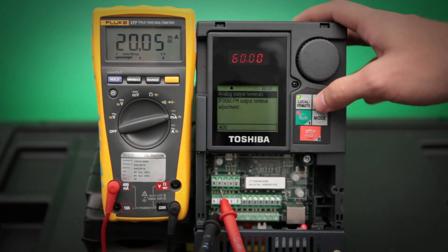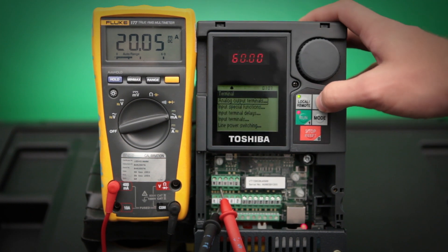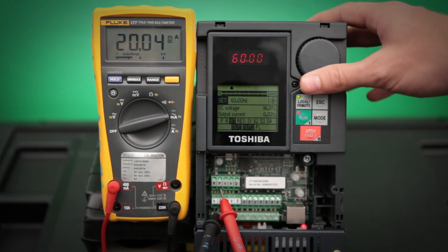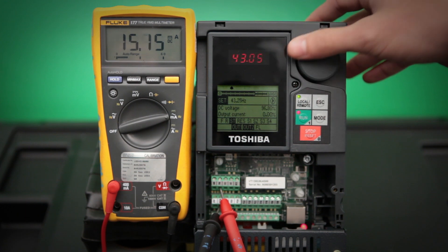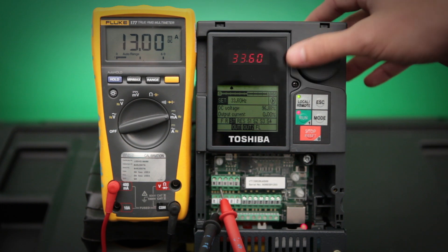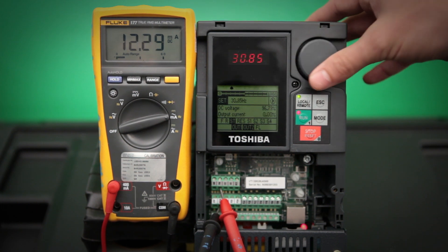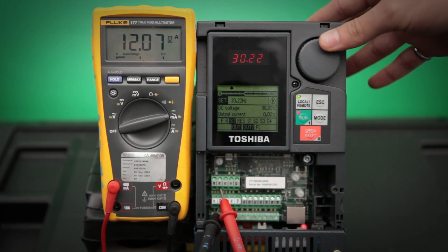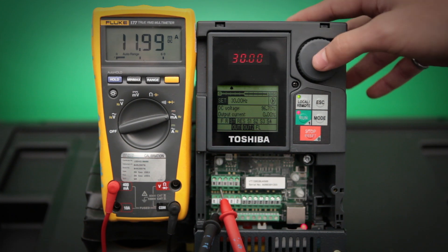Once we have that set, we want to make sure that our meter is calibrated. So let's push our escape button to go back out to our main screen. Set the drive to a frequency of 30 hertz. Really what we are looking for here is that meter display to read 12 milliamps while the drive is running at 30 hertz. Make sure that's around 12 milliamps.